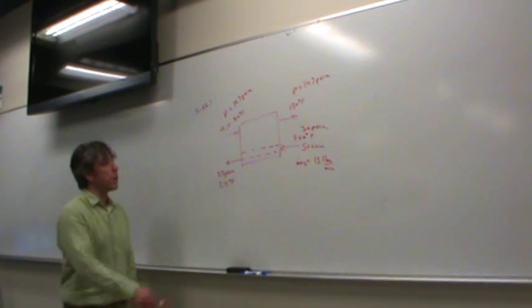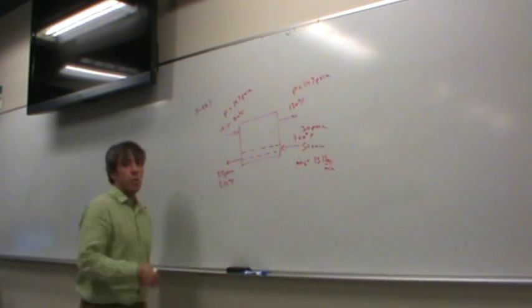In fact, if you want to measure it, you have to use a water manometer, or an electronic instrument that's as sensitive as a water manometer. So, anyway, it's a very small pressure drop. Now, this steam has some pressure drop. You guys said the reason it had that pressure drop is because of its temperature change. I disagree. I think the reason for that pressure drop is probably because this pipe is not quite as open as it could be. Maybe the velocity is high enough that the frictional effects of viscosity of the steam make a difference, I don't know. But basically, there's a little bit of pressure drop across the heat exchanger.